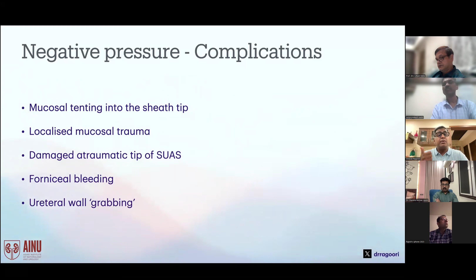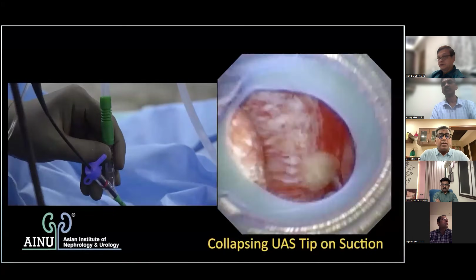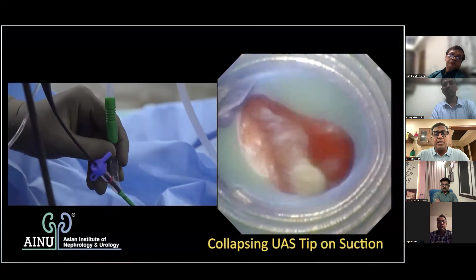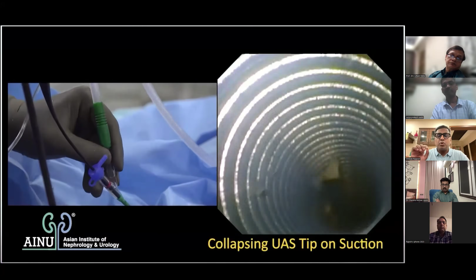They do cause more damage. And this can result in a fornicial bleed when you enter all the way into the calyx and rupture the fornix. Ureteral wall grabbing can also happen if the sheath is falsely positioned in the ureter and you keep activating the suction. So this is what I was talking about, the collapsing tip of the suction access sheath. Just look at the tip. As and when you activate the suction, the tip collapses. This soft mechanism is actually a safety mechanism, and if it is damaged, you're definitely going to damage your ureter.